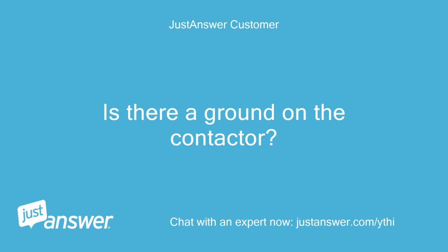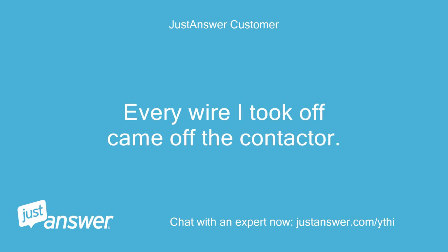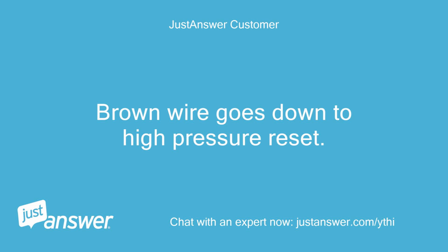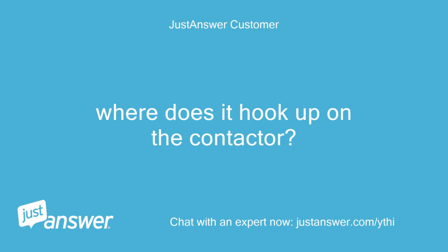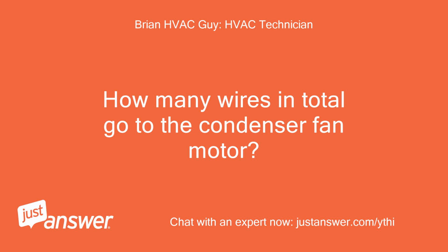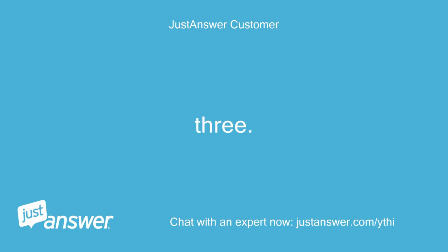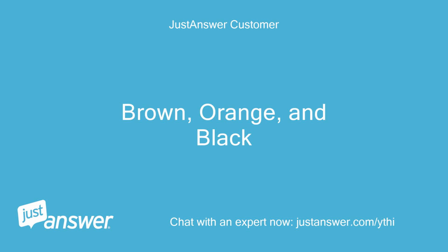Is there a ground on the contactor? Every wire I took off came off the contactor. Brown wire goes down to high pressure reset. Where does it hook up on the contactor? How many wires in total go to the condenser fan motor? 3. Brown, orange, and black.